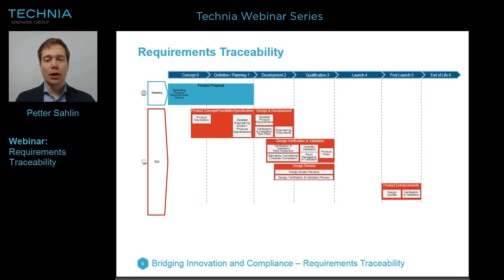For design review, we use these tools continuously through the reviews, and that's one basis for our decision making as our qualification is completed. After post-launch, we also want to reconnect, either because we have complaints registered on the products, or we just want to plan and execute a design update. And then, of course, we want to reconnect to the initial design controls, the initial design intent, and the previous test protocols, the previous test schemes, and the previous validation. So that's where it comes back in a post-launch phase.